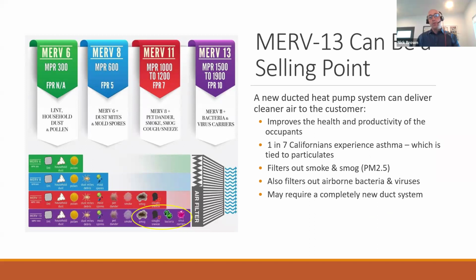But I did want to cover why MERV 13 made its way into the code, because I think it's a selling point for us in the HVAC industry. In this chart on the left, you see MERV 13 filters in purple capture additional smaller particles than the MERV 6 and MERV 8 that we're used to in the past, including bacteria and viruses. I think we can sell that to our clients, right? Hey, with this HVAC retrofit, I'm gonna clean your air with a MERV 13 filter every time your HVAC system runs. And that's going to pull a large portion of bacteria and viruses out of your indoor air. We just went through COVID, right? That's a pretty compelling sales pitch, I think, for any HVAC professional.